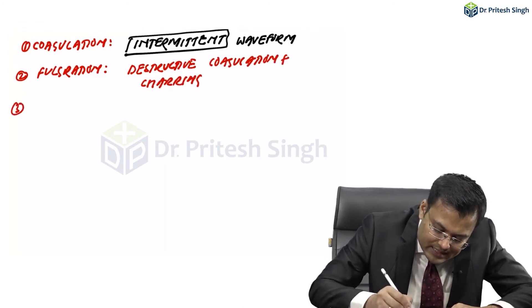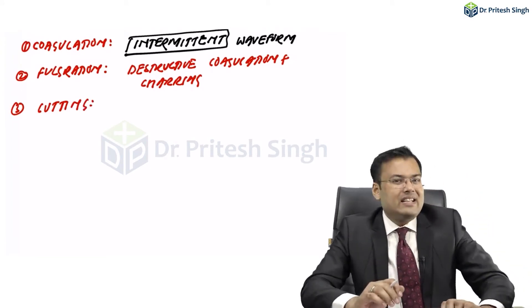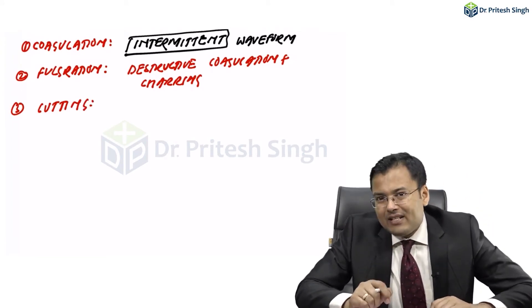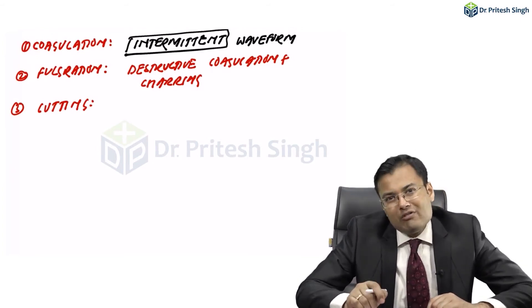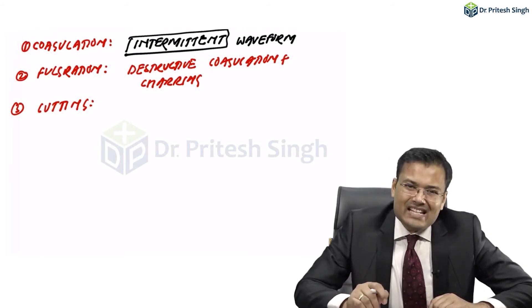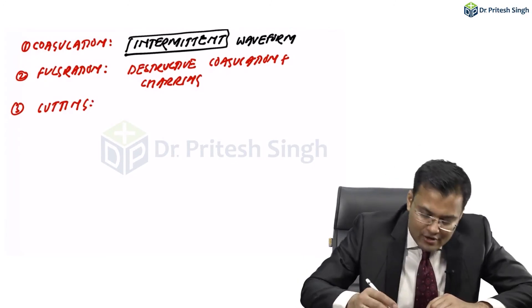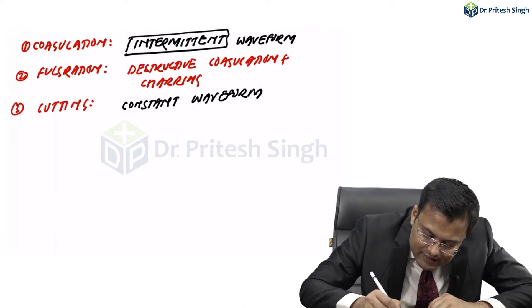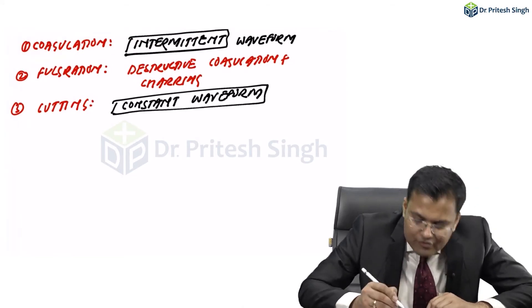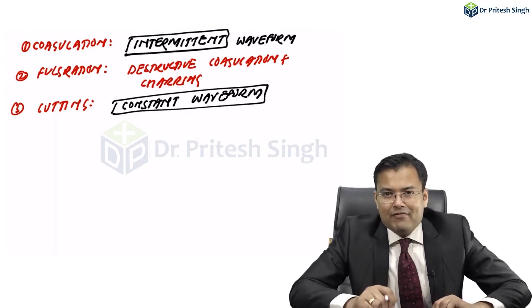The third effect is cutting. In cutting, the cautery is activated with a continuous or constant waveform. Be careful: for coagulation, the cautery is activated with an intermittent waveform, whereas for the cutting effect, the cautery is activated with a constant waveform.